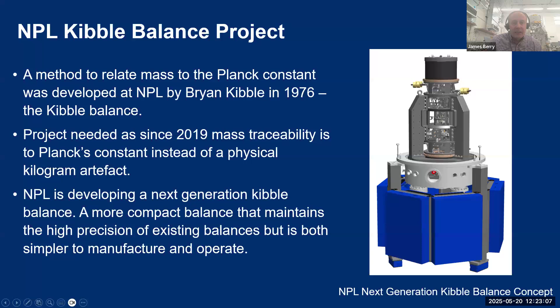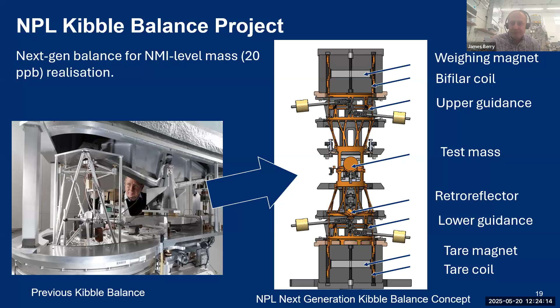This is where we're going from. We want to develop a balance that has about 20 parts per billion realization, so you're talking about microgram level on measuring a kilogram. The previous kibble balance, in the photo on the bottom, is based on an old two-pan balance. It was hideously difficult to align the components precisely enough. You need to get angular alignment to within about 30 microradians, and it usually took about a week to align the instrument before you could do a set of measurements. What we want to go to is something more compact, which allows just direct vertical motion with no motion on the other axes, or torques around them either. Our design engineers have come up with a guidance mechanism that allows purely vertical motion and no motion around the other axes. This is the concept that you can see in the image on the right.